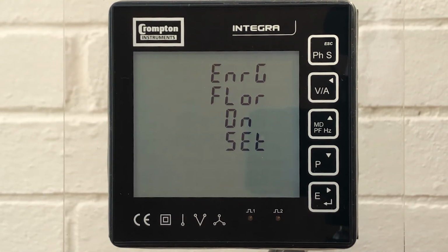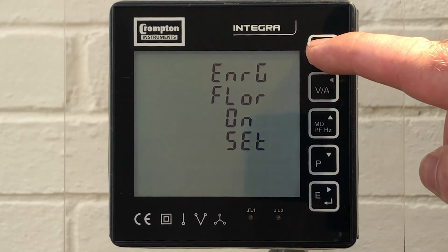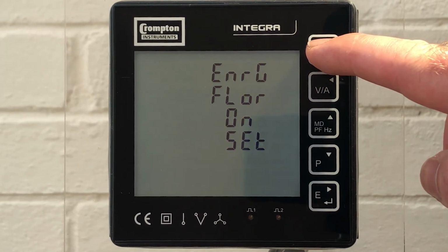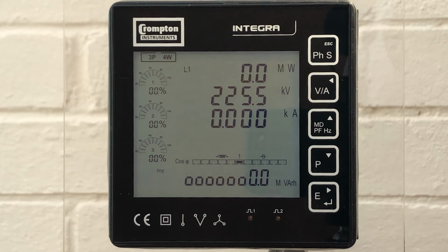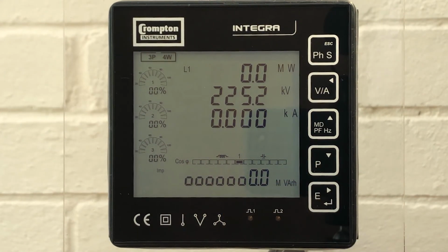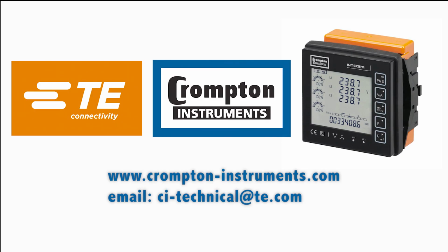Now that's set, if we hold down the escape button for 2 seconds, return to our main screen, you can see that the warning triangle has now disappeared from the display, which indicates the energy floor is working correctly. That concludes the hardware and setup guide for the Crompton Instruments 1222 self-powered unit.